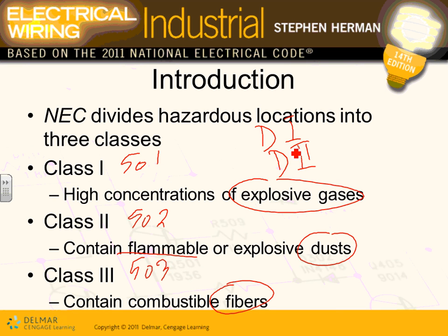Same thing for the dust. Same thing for the fiber. For the fiber, guys, the place where they process the paper is a Class 3. And the place where they store the paper and fibers and wheat is a Class 3 Div 1 or a Class 3 Div 2. So the storage area, the place where they store it, is a Div 2. It's lower hazard. Div 1 is a higher hazard. So every one of these classifications is divided into two. Div 1 is the higher hazard. Div 2 is the lower hazard. Does that make sense? Everybody understand the division?